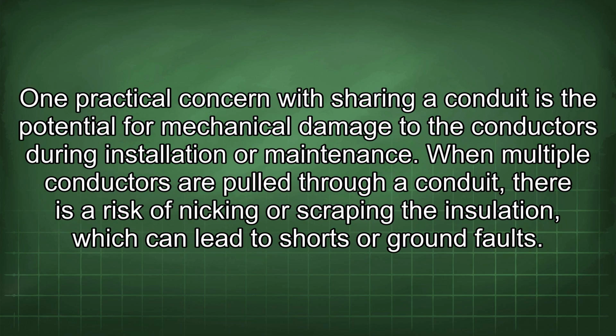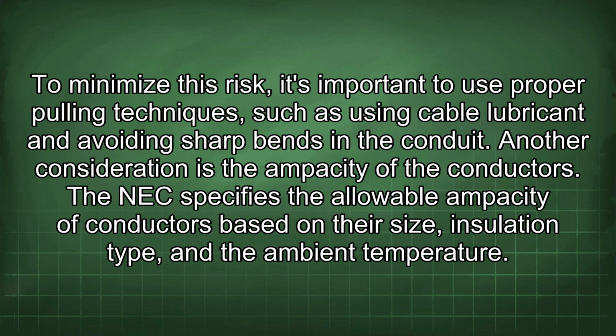One practical concern with sharing a conduit is the potential for mechanical damage to the conductors during installation or maintenance. When multiple conductors are pulled through a conduit, there is a risk of nicking or scraping the insulation, which can lead to shorts or ground faults. To minimize this risk, it's important to use proper pulling techniques, such as using cable lubricant and avoiding sharp bends in the conduit. Another consideration is the ampacity of the conductors.